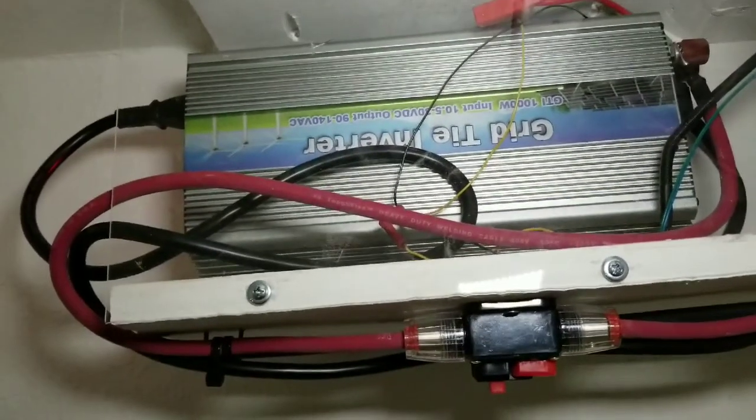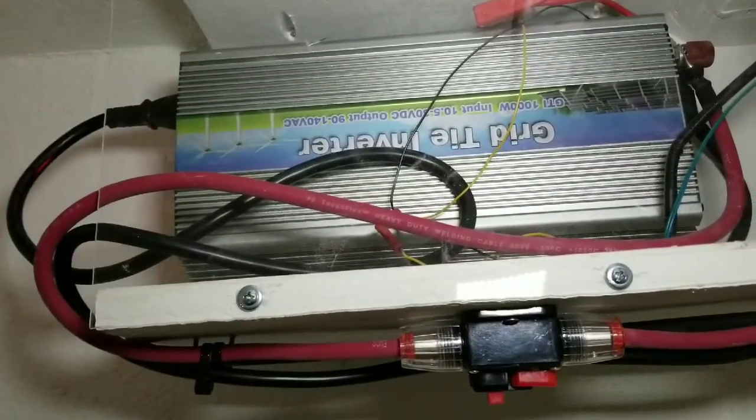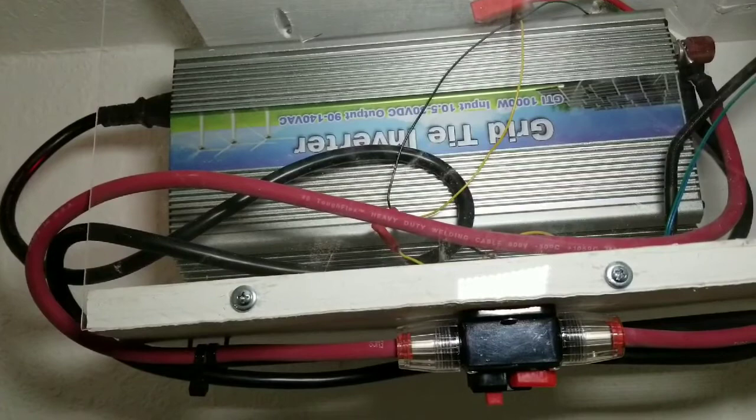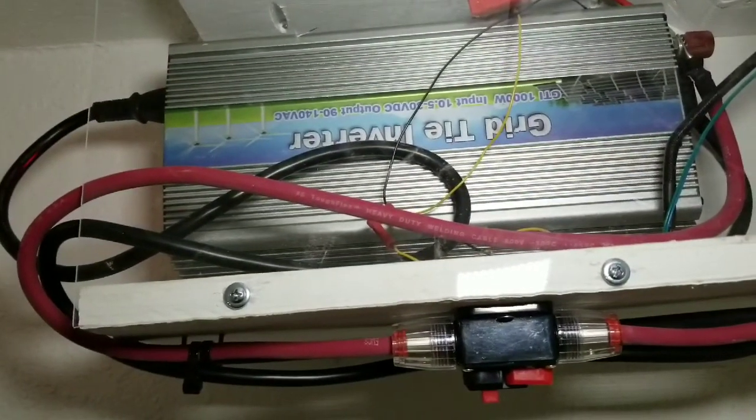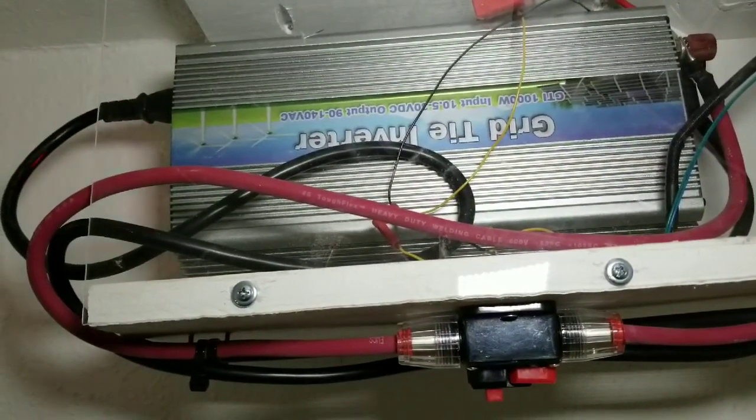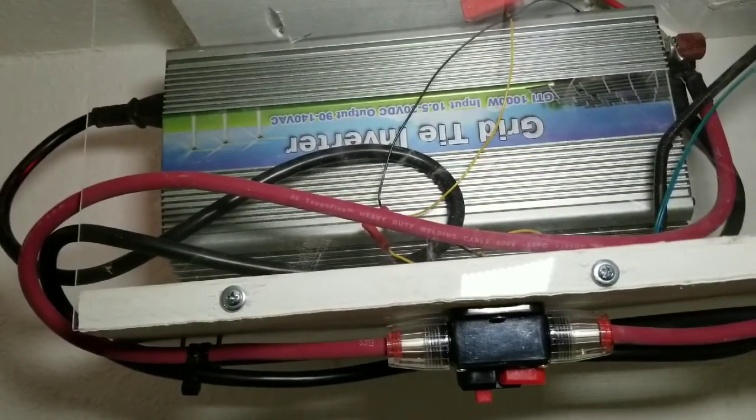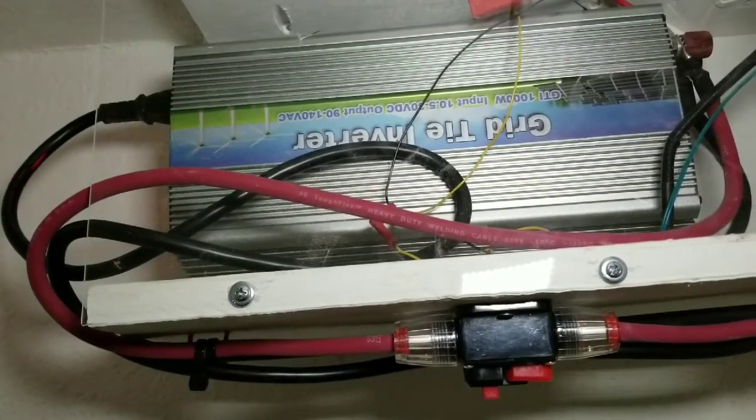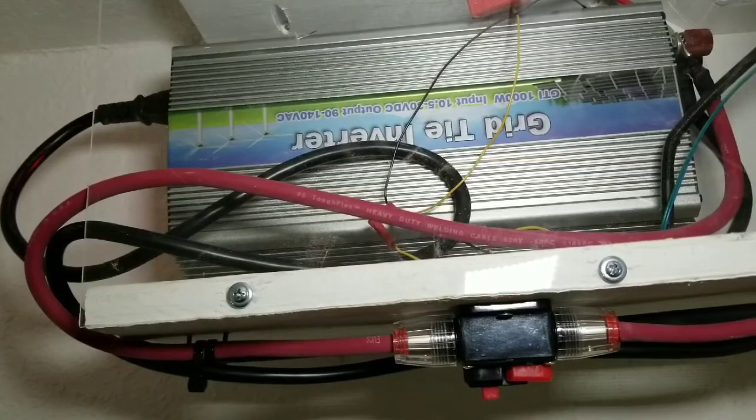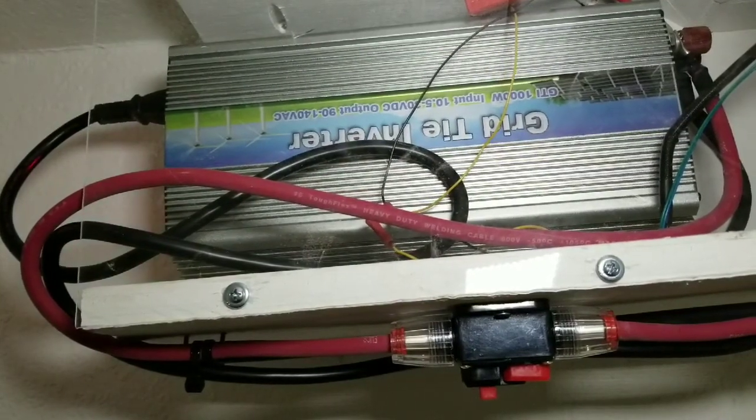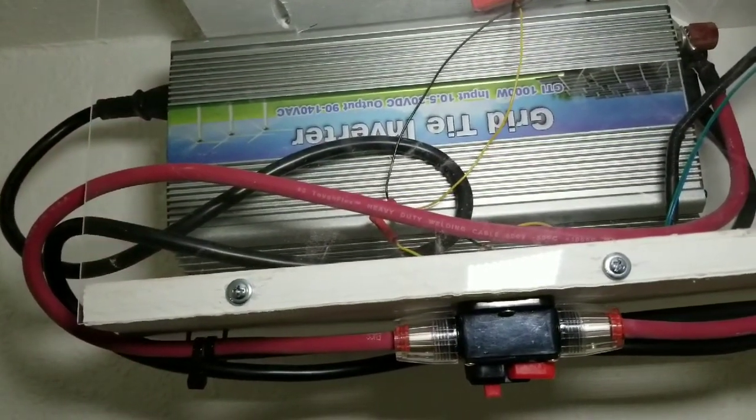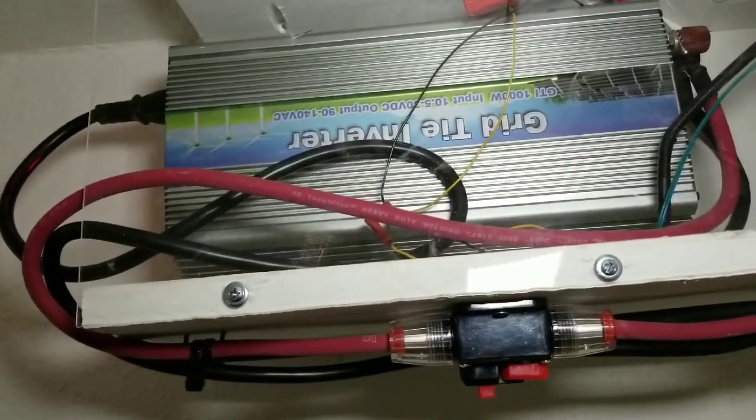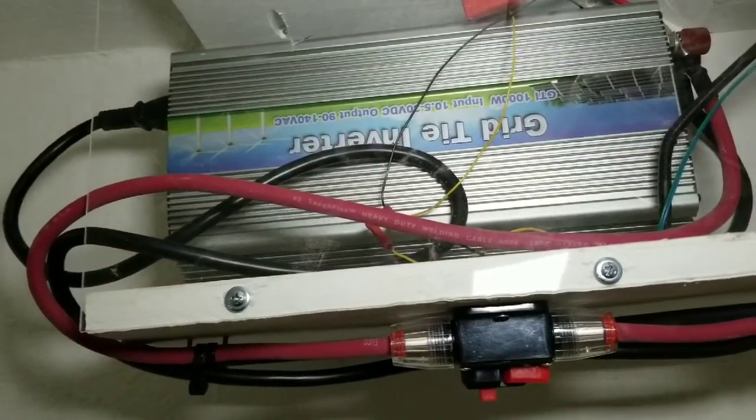The main reason is because you can potentially cause a fire with them. So if you think about it, the breaker is at the other end, and if it's a 15 amp breaker and this is pushing power into that circuit and you're also drawing it from the other end, you can potentially start a fire in your wiring.